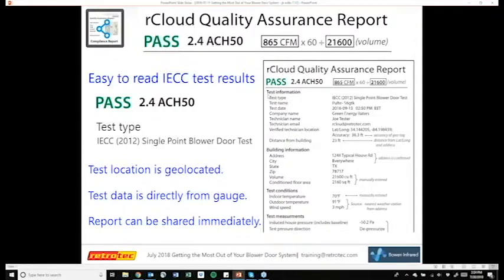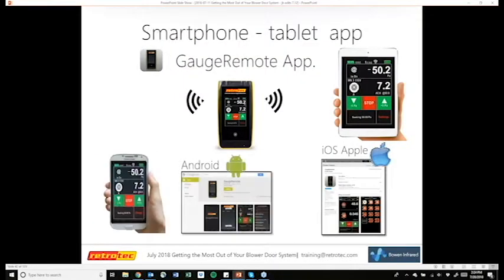And so another app that we have available that makes life a little easier is the Gauge Remote app. And basically what this does is it mirrors the screen on your gauge to your device, whether it's your phone or tablet. That way you're free to walk around the house and control your fan from anywhere in the house. So if you want to have your phone in one hand to control the fan and a smoker in the other to find leaks, or your phone in one hand and a thermal imaging camera in the other to walk around and control the fan without having to run back and forth or have a second person, this makes things a lot faster. It's also really handy for duct testing, especially if you have your duct tester set up in the conditioned space and then your air handler's up in an attic or down in a crawl space. This allows you to go check for leaks without having to have a second person or run back and forth to the tester and the air handler.